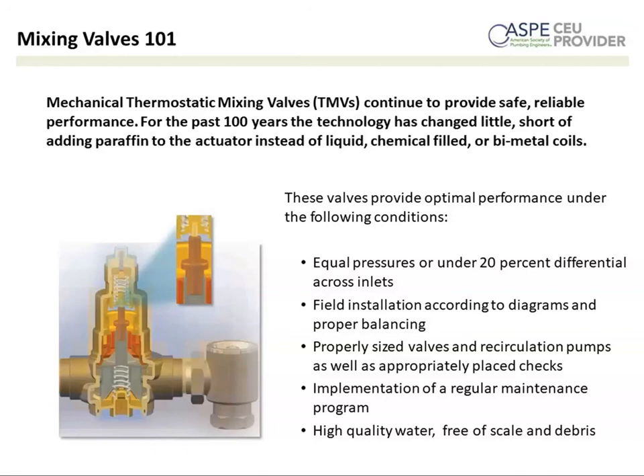But clearly, the installation and the system design is critical. Making sure that the valves are properly sized. We talked about that earlier. You don't want a valve that's too big because it'll struggle at lower flows to control. Having a recirc pump that's properly sized, make sure that checks are in the right places so you don't have cross flow. An implementation of a regular maintenance program is critical. These have to be looked at. And obviously, making sure that your water quality is very good. It's free of scale, debris, those types of things. So that's very, very critical for thermostatic mixing valves. It's important for digital as well, but very critical for traditional thermostatic mixing valves.